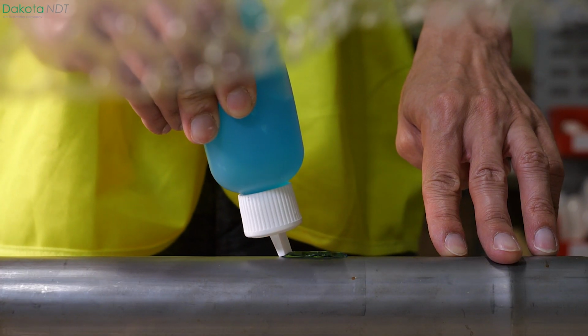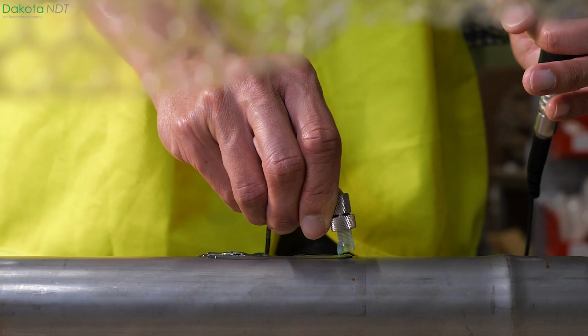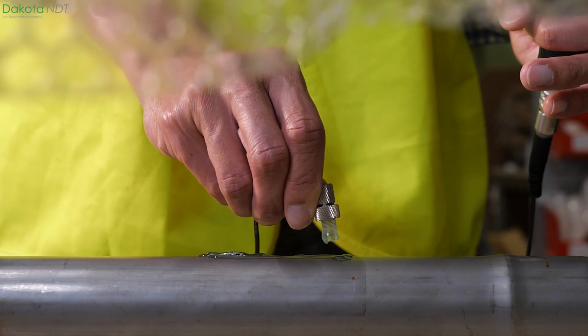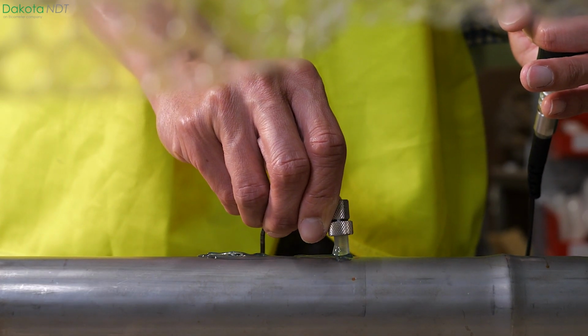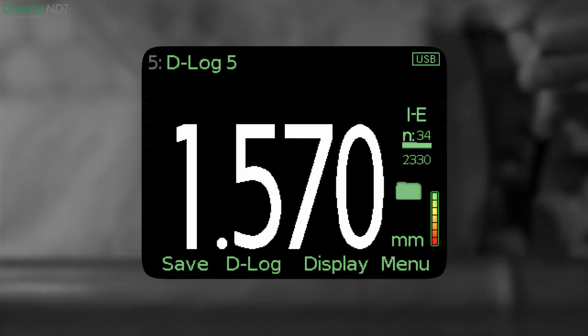Using a very small amount of ultrasonic couplant, press the transducer flat against the surface. When the transducer is placed on the material, the reading stability indicator will show how strong the ultrasonic signal is. A red or orange bar means that you need to adjust how you're holding the transducer. But if the bar is full, this means you are going to receive accurate and reliable measurements.